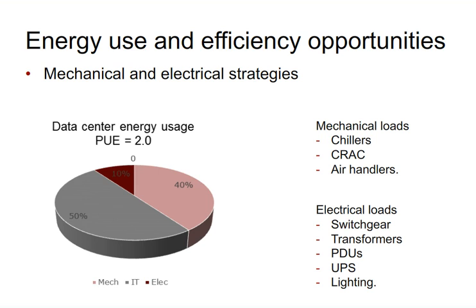Looking at a data center with a PUE of 2.0, you can see the energy breakdown between IT equipment, electrical, and mechanical. This is an older-style system where mechanical could include chillers, CRAC units, and air handlers, and electrical loads include switchgear, transformers, PDUs, UPSs, and lighting. Some of that energy, such as transformer losses, is essentially waste energy.